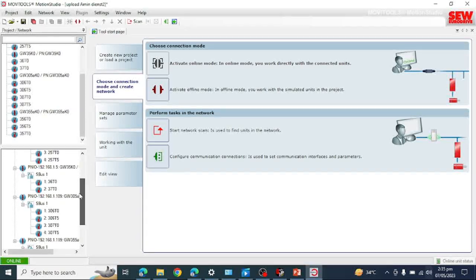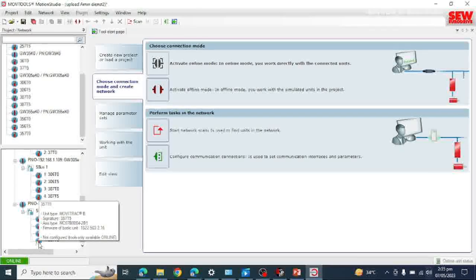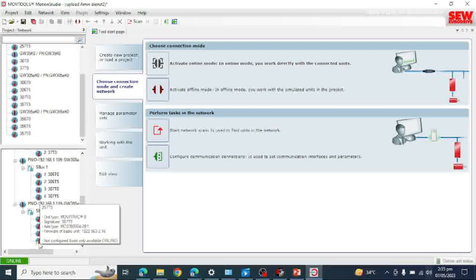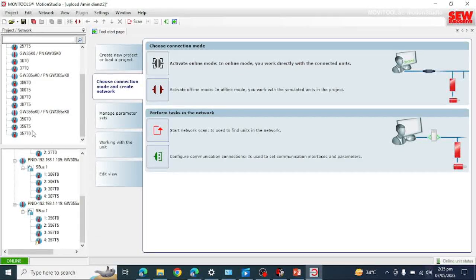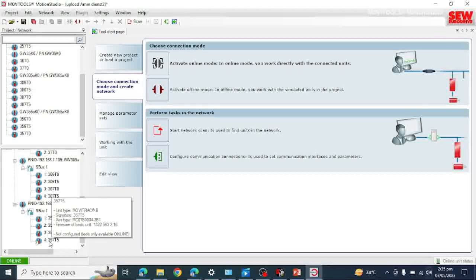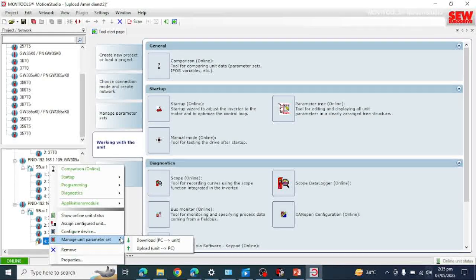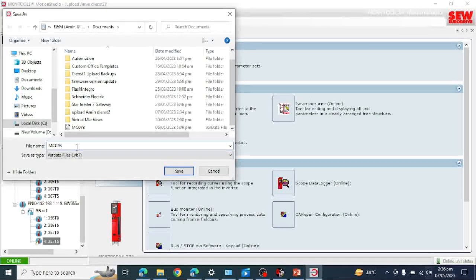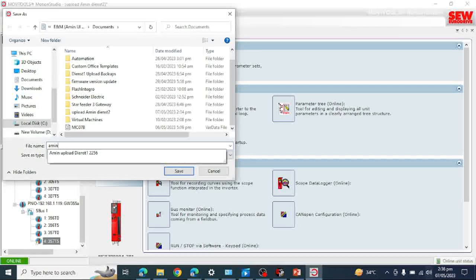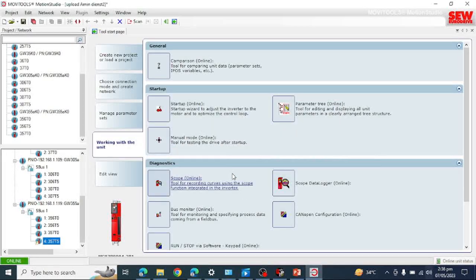On the project window, all devices are clear except one, which is marked — this means that drive is not configured in this file, because I deselected it earlier. To take the backup of this single drive, right-click on the drive and click Upload. It is now asking where to save the file. I will save it as 'Amine' and click Save. It is now saving the file. These are the two ways to take a backup of the drive.